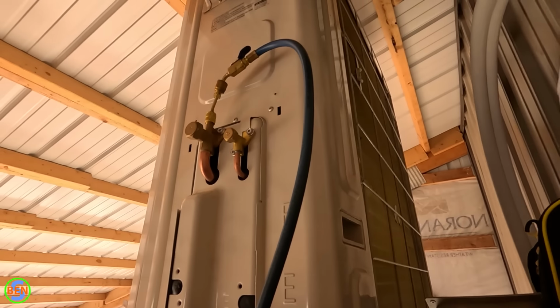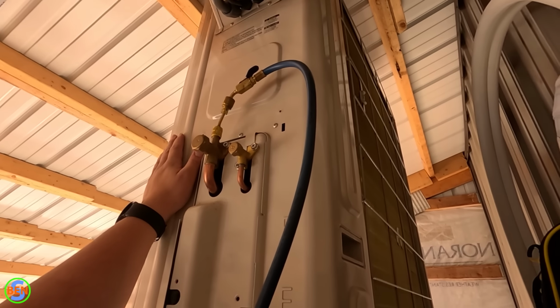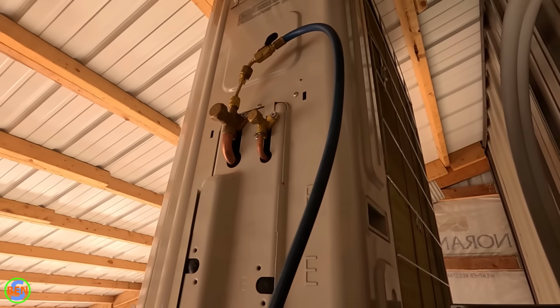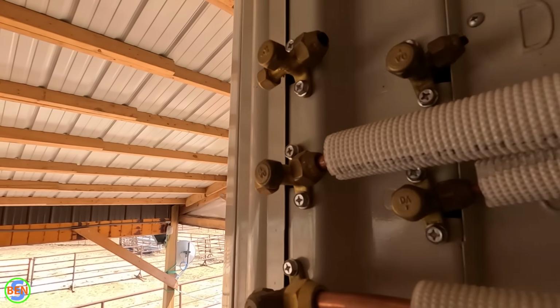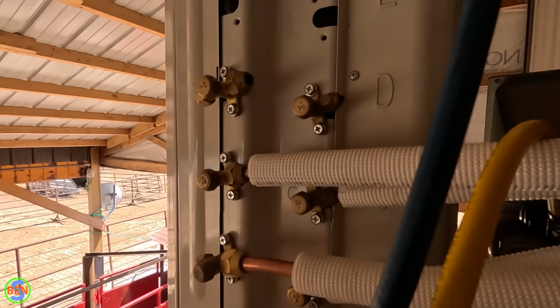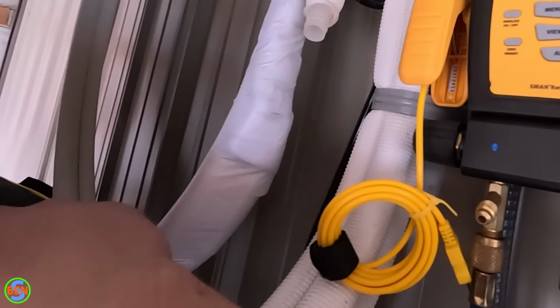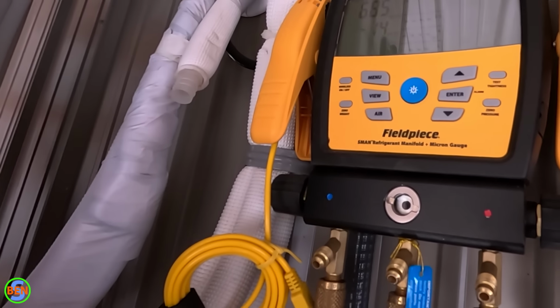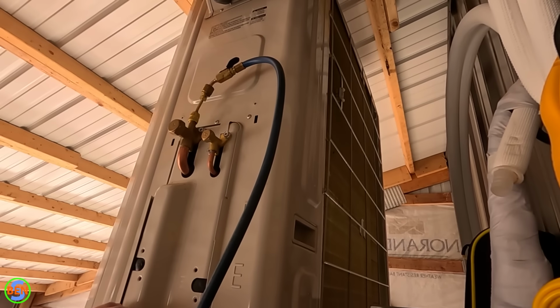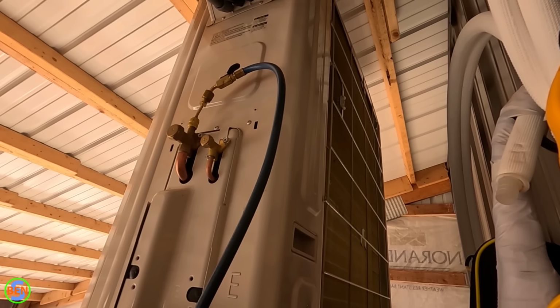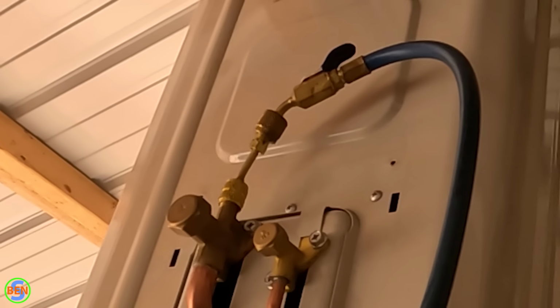After your vacuum pump has been running for that half an hour, you'll then be good to go to shut off the high side and low side valves on your gauges and then shut down your vacuum pump. Now hopefully your hoses have valves on them, because you would want to turn the valve off on the vacuum pump actually if possible, but if not, it can still work. Just keep it in mind that if you're going to buy some hoses, it's a really good idea to buy some that have valves on them.